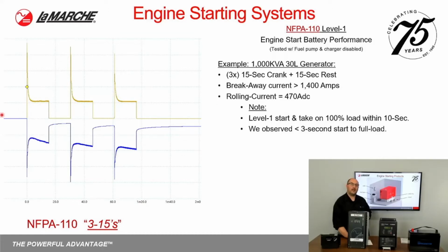NFPA 110 will ask that when sizing the battery, it is capable of producing 15-second cranks that also have 15 seconds of rest in between. What that means is that the battery must have sufficient energy to accomplish that many cranks, but it also must have sufficient power to deliver the starting current. So let's look at this in terms of breakaway current.